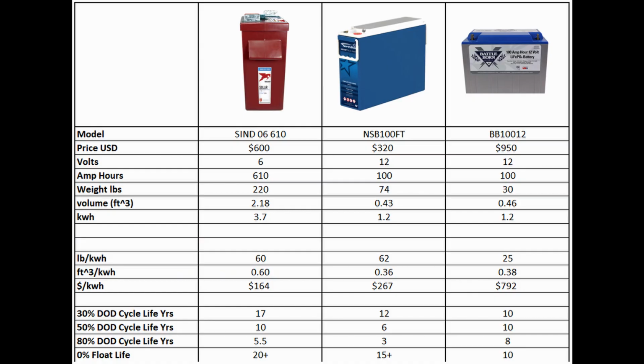This is why I recommend backing off the charge voltage from what the manufacturer recommends, as it will significantly increase the float life and allow the cycle life to dominate where lithium batteries shine. For float life or backup power applications where it's stored charged 24/7 but not cycled, I'll assume the lithium battery will achieve its 10-year life. Again, it is the laggard of the three.